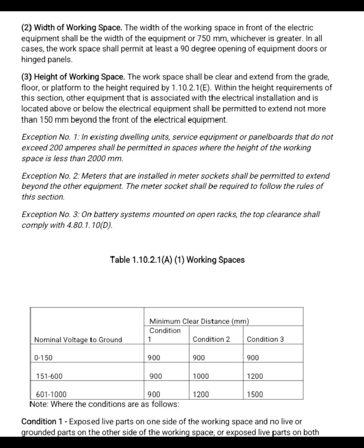Number 2. Width of the working space. The width of the working space in front of the electrical equipment shall be the width of the equipment or 750 mm, whichever is greater. In all cases, the workspace shall permit at least a 90-degree opening of equipment doors or hinged panels.